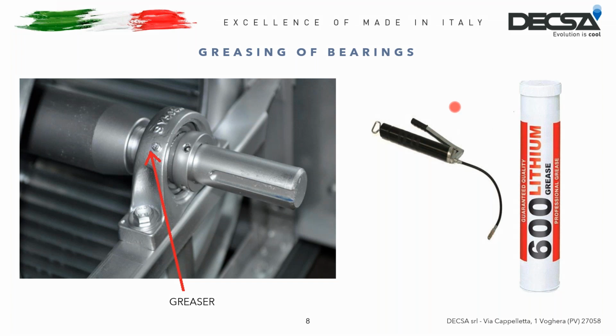Now we can move on to greasing the bearings. I remind you, every 4 months or 3,000 hours of operation. Above each support, there is a lubricator to which the pump nozzle must be connected. This is the nozzle and this is the pump, the proper pump. This pump must contain a lithium grease cartridge for bearings. The quantity of grease to be used corresponds to 3 pumps, just to understand the quantity, a soup spoon. Again, turn the transmission manually for even distribution.